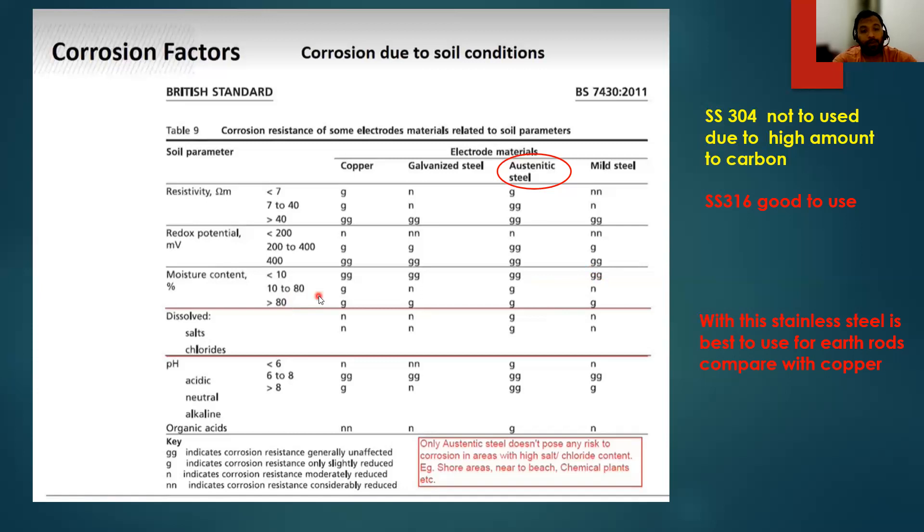austenitic steel slightly reduced, and mild steel moderately reduced. If you see all those parameters, which material is good? Austenitic steel is very good, and after that copper is good, then mild steel, then galvanized steel. Based upon this, you have to select your earth electrode.